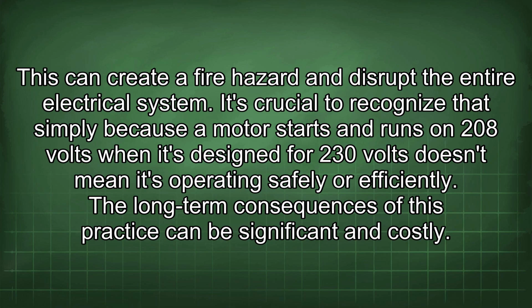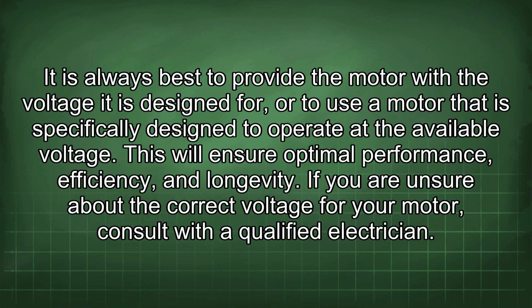It's crucial to recognize that simply because a motor starts and runs on 208 volts when it's designed for 230 volts doesn't mean it's operating safely or efficiently. The long-term consequences of this practice can be significant and costly. It is always best to provide the motor with the voltage it is designed for, or to use a motor that is specifically designed to operate at the available voltage. This will ensure optimal performance, efficiency, and longevity.